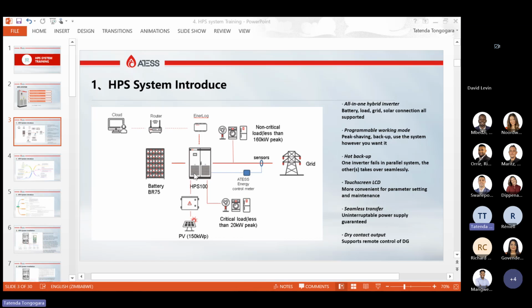So inside the HPS, you can connect your grid. So we have one AC input. So in the event that you have generator and grid at the same time, you need an ATS from Atess, or if you have an already existing ATS on site, you can also make use of it, provided it is a dry contact that tells us whether the grid is running or the generator is running.